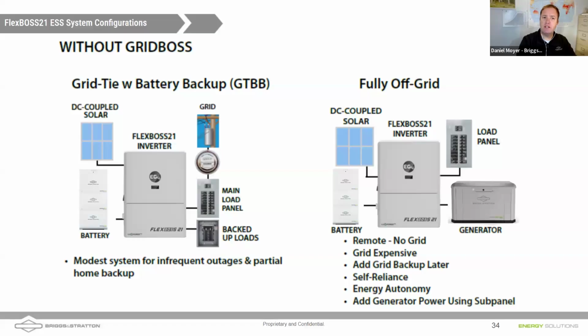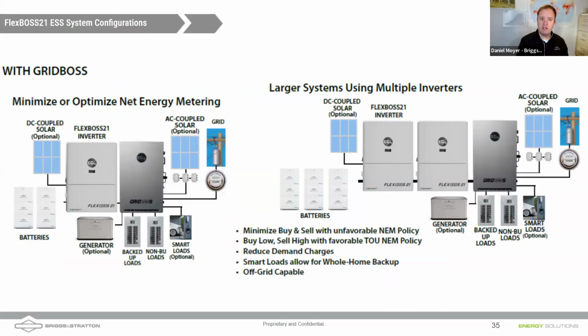Another example there is the FlexBoss being used in a partial home backup situation. Very similar, but we're not going to be able to bring in all 200 amps. We're going to want to use a backfed breaker on the bottom of that load panel with the hold down kit. We could maybe put in a 90 amp breaker, and using PCS CRD control, we can put in a larger breaker than, say, a 40 amp breaker that would typically be allowed on a 200 amp panel with a 200 amp bus, meeting that 120% rule. Definitely flexibility, but I think where most of the flexibility comes in is when we bring in the GridBoss.